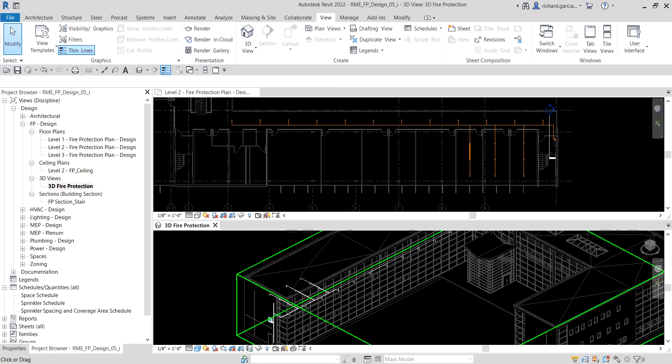After tiling the views, it is important to recognize the distinction between sizing and manually changing the diameter. Changing the diameter, width, or height of a pipe on the options bar is not considered sizing in Revit. Sizing is performed using the sizing tool to size the pipe based on a series of parameters and calculations. The calculated size of a pipe is the result of the sizing tool, not a manual change.